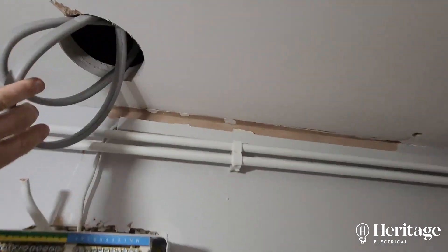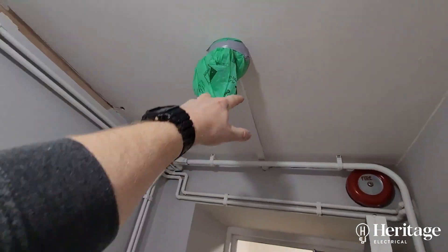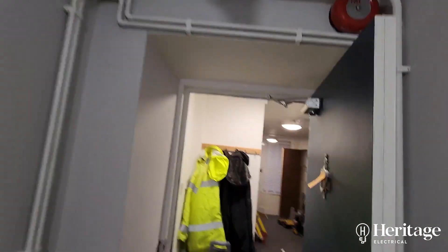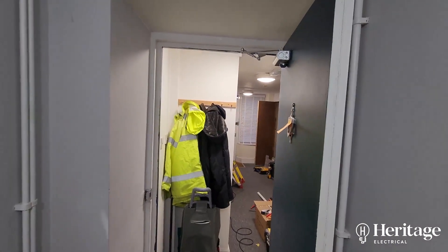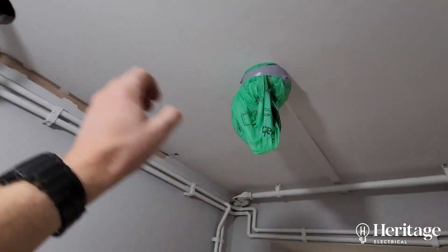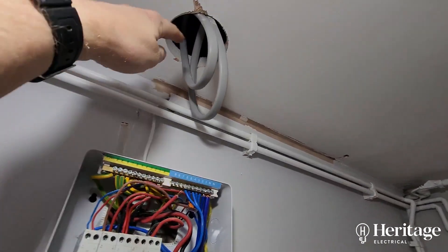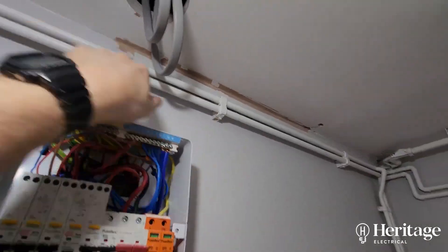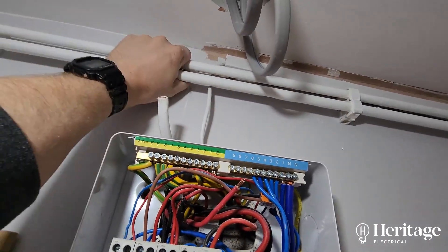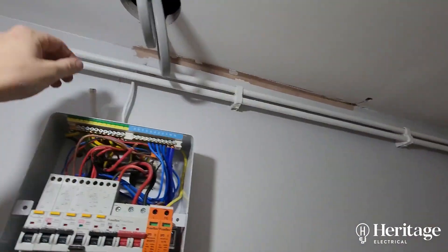I've rewired it now. I've taken all the old trunking off where it just popped into the ceiling. I've also covered the fire alarm up - he's got smoke detectors but also a fire alarm linked to the building as it's a multi-storey set of flats with multiple occupancy, so I made sure that was covered because all this dust would have set it off. We've cut a hole up there and we're going to run a piece of conduit out into the new board. I want to lose that piece of trunking and get rid of any cables going behind these hot heating pipes - anything going behind those will be contained in a piece of conduit.